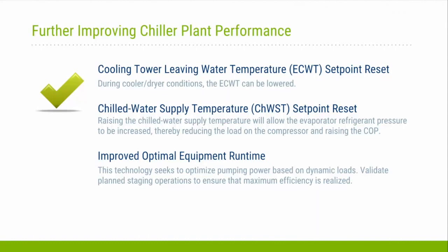And then some of the other things that are not on the slide that you might want to consider are the things that we saw that were improved, such as staging of chillers. Again, if you have 2 or more chillers, the ability to run only 1 chiller. Some of the newer chiller vendors, however, will say that they want to see you run 2 chillers because their optimum kW per ton performance might be where they're 50% or less loaded. So all those things need to be taken into consideration, and obviously the vendor would look at all that and make sure that they're optimizing staging of chillers. So let's go to the next slide, please.